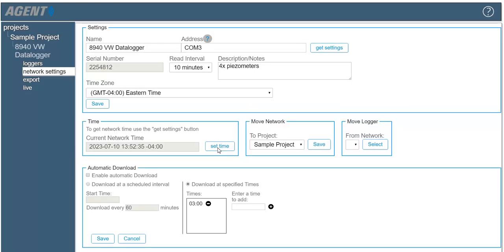The logger will now begin collecting data. Please note that if the data logger batteries are removed, depleted, or replaced, or if the power is cycled, the time must be sent to the logger before it will resume data collection.